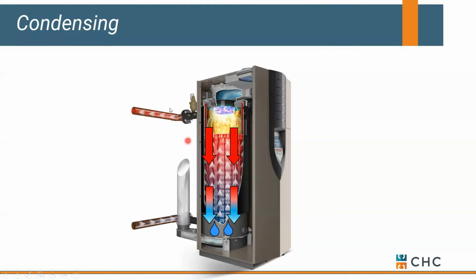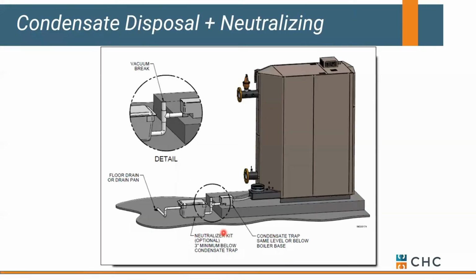We have to get it out of the boiler. Nothing happens on our system side. That's simply a closed loop system, pipe that's enclosed with water. Nothing's going to change there. It's on the boiler side, or our combustion side, that we're going to get some moisture out.